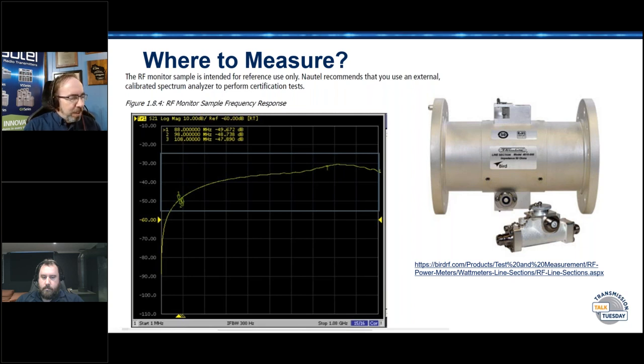Now, getting back to calibration, Eric mentioned this, and it's a good answer for William too: you can have a second calibration done after a couple of years. Get your through line section and sample elements calibrated, do it again in a couple of years, and if the response hasn't changed more than 0.1 dB or so, and everything's still fine, then you're probably good to back your calibration schedule out quite a bit. So, rolling curve, you'll establish your calibration frequency based on how often it ends up needing to be calibrated. What's the FCC say? As often as required to maintain compliance. They don't tell you how often that is. That's up to you. So that's the kind of thing we're looking at there.